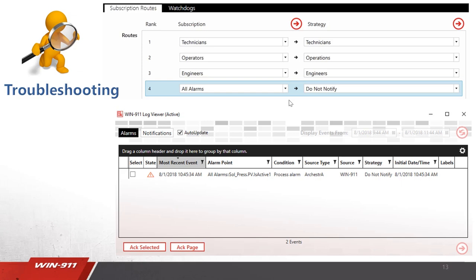Well, maybe going back to our configuration, there's some case sensitivity with the alarms. You need to make sure that what you configure for your route over in WIN911 needs to match how you have the case sensitivity set up for your alarm over in your SCADA. Or maybe you just didn't filter on that correct criteria. If you use this catch-all at the bottom for all alarms to go to some strategy, whether it's do not notify or some other strategy you decide, you can use this as a troubleshooting method to make sure your alarms go to the appropriate people.